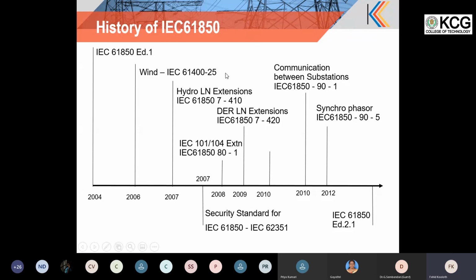Then they wanted interoperability with the existing systems, and exchange over 101 and 104 was one of the key scenarios. So they defined a mapping over 101 and 104, which is done in 80-1. Then for communication between substations, they defined a standard named 90-1. Then they wanted to exchange data from phasor measurement units, nothing but PMUs, to the control center, going to the super PDC. So they defined 90-5, which carries sampled values over UDP. It needs to go beyond the substation, so they needed a UDP layer to transmit to the control center scenario. So they defined 90-5.